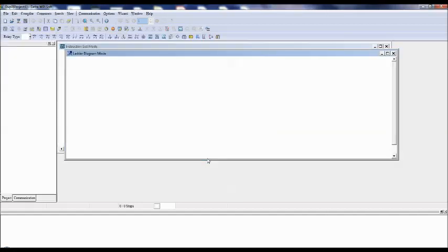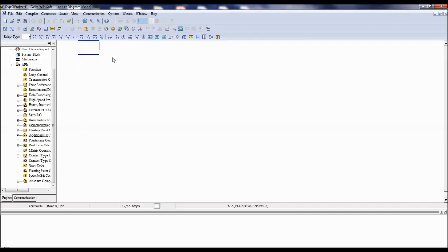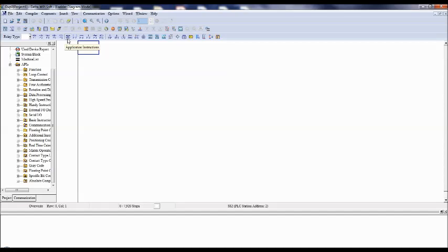So now this is the ladder logic screen. I will explain the simple features here. This is the command tool, and basic commands are there. For example, F1 is normally open, F2 is normally closed, F3 is rising edge trigger switch, F4 is falling edge trigger switch, F5 is set point, F6 is application instruction where you can find counter, timers, reset function, set function, etc. F7 is output coil, F8 is horizontal line, F9 is vertical line. F11 is inverse logic, F12 is comparison. These are the shortcut function keys.